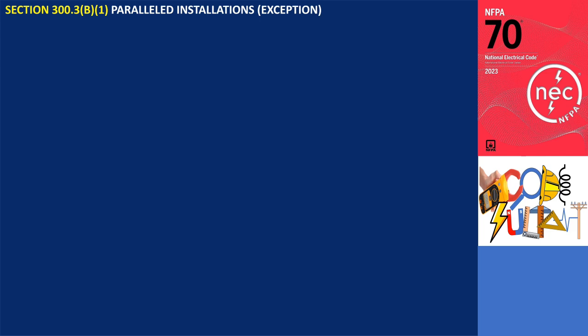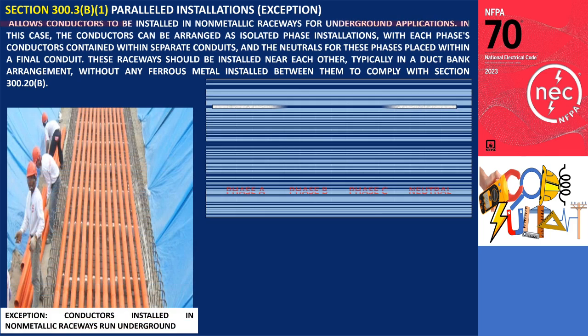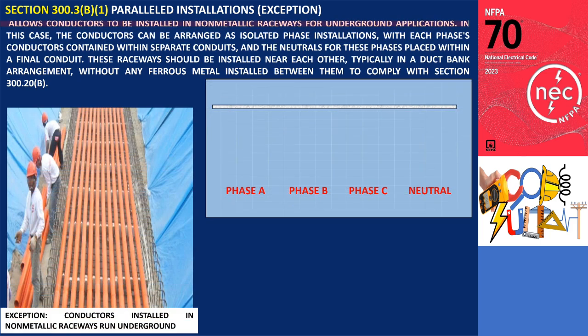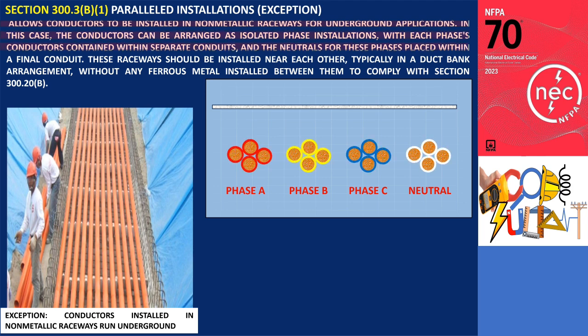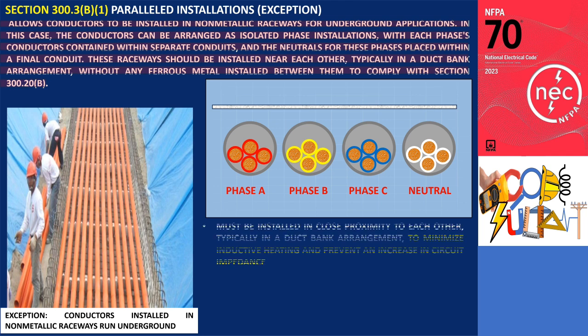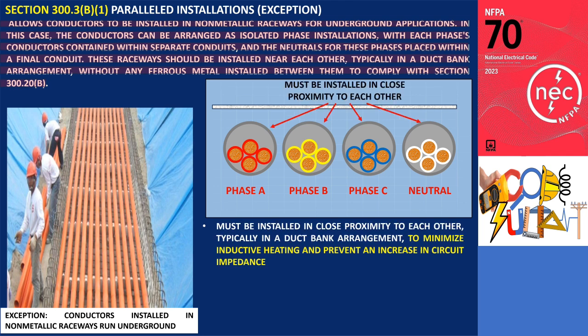There is an exception that allows conductors to be installed in non-metallic raceways for underground applications. In this case, the conductors can be arranged as isolated phase installations, with each phase's conductors contained within separate conduits and the neutrals for these phases placed within a final conduit. These raceways should be installed near each other, typically in a duct bank arrangement, without any ferrous metal installed between them to comply with Section 300.20.b. Installing raceways near each other is crucial to minimize inductive heating and prevent an increase in circuit impedance.